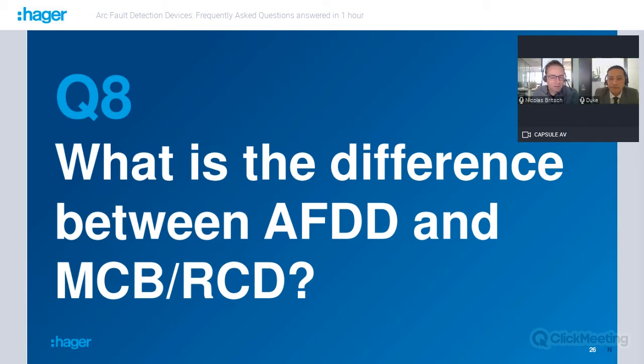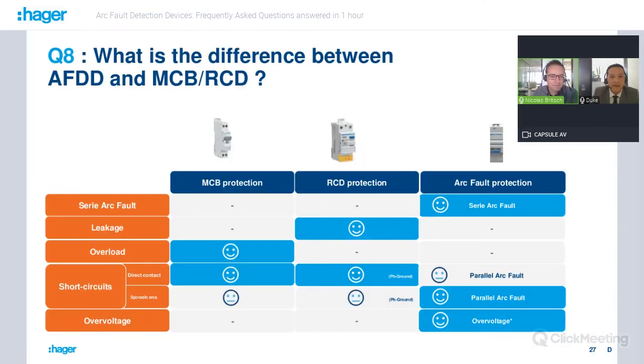Can you explain a little bit more what is the difference between AFDD and MCB, RCD? MCB is for miniature circuit breaker and RCD for residual current device. It's a very pertinent question. First, we take a look at the functionality. The MCB protects against overload and short circuit, and in case of direct contact. The RCD protects in case of leakage and short circuit phase to ground. And arc fault protection completes the protection against series arcs and parallel arcs, and in the case of Hager's AFDD, includes overvoltage protection.